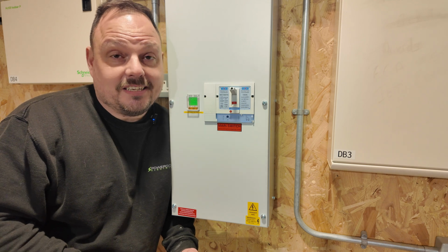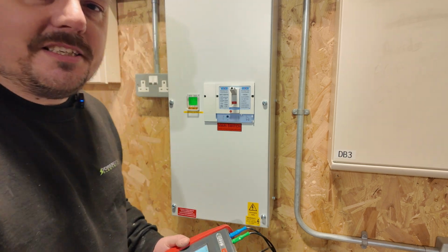And we can still satisfy the intent of BS7671. So happy days. Yeah, so that was a nice little test just to demonstrate here. And it was interesting to see how this did see what was going on in terms of that leakage current. So we had it set down to half time, so 15 milliamps. That is exactly what was showing happen through the test instrument.